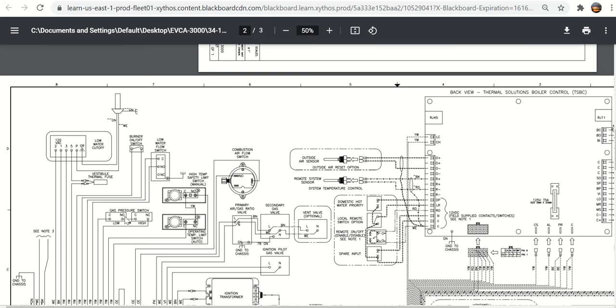Here is your combination high and low gas pressure switches. Here is the high limit safety, and then the operating limit. It's required on all boilers that they have a separate high limit control. We talked about this when we talked first about the triple flex boiler having the dual element thermistor for safety circuit, but this Thermal Solutions is sticking with a standard Honeywell high limit, and then they have a secondary operating control here, even though over here on the TSBC you can set a set point.